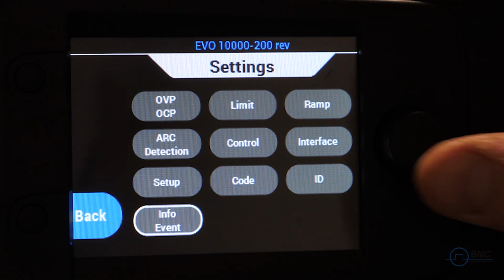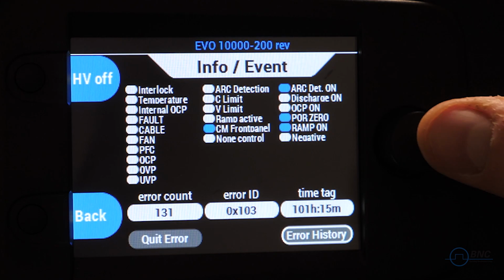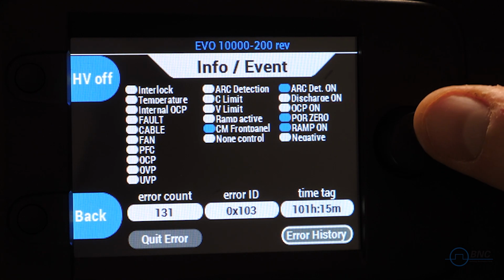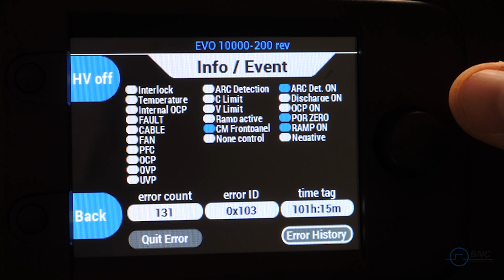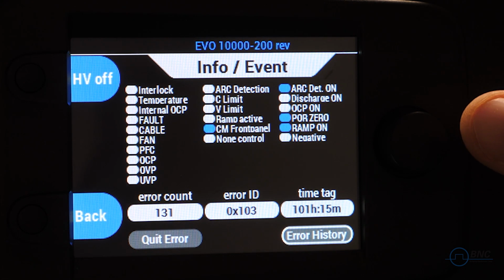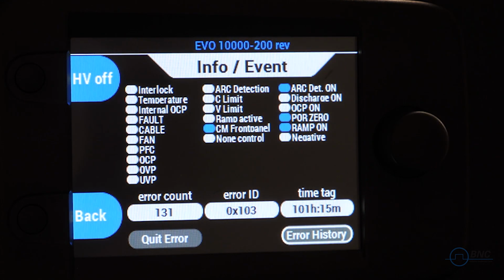Here we actually have the info and event log. This can come in handy if there's any kind of error, or if the unit overcurrents and shuts down, we can go into here and see what happened. We can see if it tripped because of overcurrent or over voltage, if there was a fault, or if the interlock just came out. So it can give us some forensic details on a failure, which really helps to troubleshoot and diagnose problems.